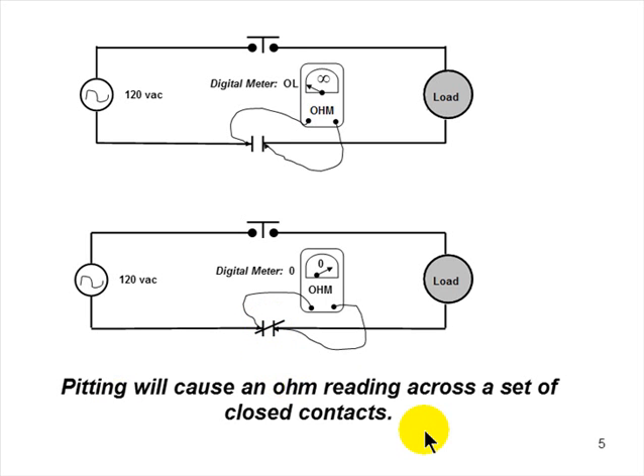What would give me a resistance reading? A dead June bug, dirt, pitting. What is pitting? Let me explain pitting. Plug a small operational device into the wall, like a small desk fan. While the desk fan is running, jerk the cord out of the wall, and you're going to see a spark. If you don't see a spark, do it at night with the lights off. You'll see a spark, however small.